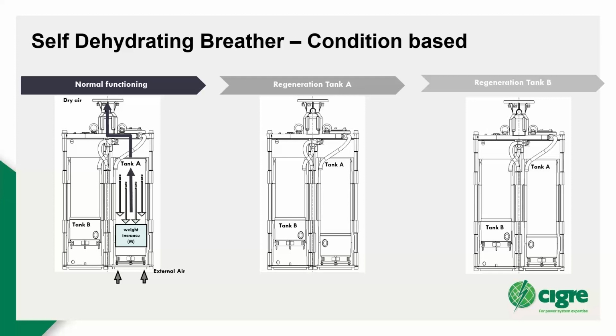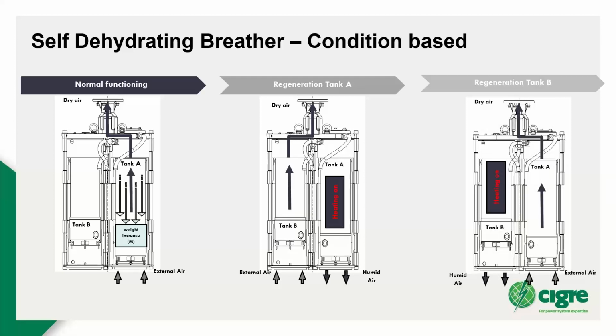At a predefined set point, tank A is switched off, the transformer starts breathing through tank B, and simultaneously the heater is switched on so that the humid air is taken out, heated, and the silica gel regenerates. Then the process repeats itself.